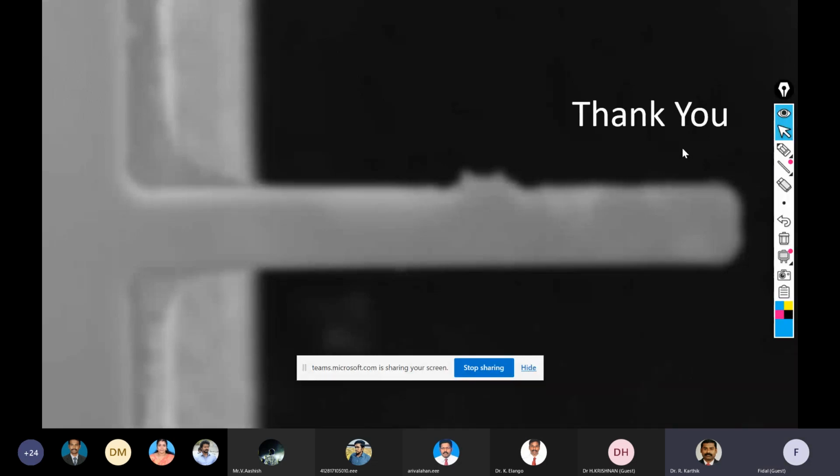Yes, we have tested the accuracy of this cantilever sensor with some clinical samples. It's more or less within plus or minus 2% or 3% compared to the clinical test. One place where cantilever sensors can really be used is with samples other than blood. Blood is very commonly used as the sample for detecting some kind of analyte.